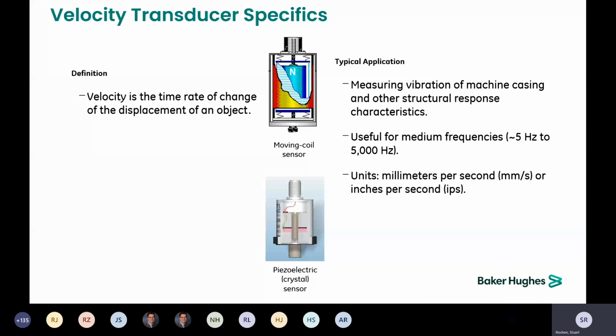Upsides are that it is a self-powering unit and it is very good for low frequencies. Some of the downsides are it has moving components, so they do fatigue and wear. So we do recommend that you do a verification of those sensors a little more often than you would a piezoelectric. Verification basically consists of putting it on a shaker table and inputting a specific vibration level and making sure that the velocity pickup is outputting the same value.